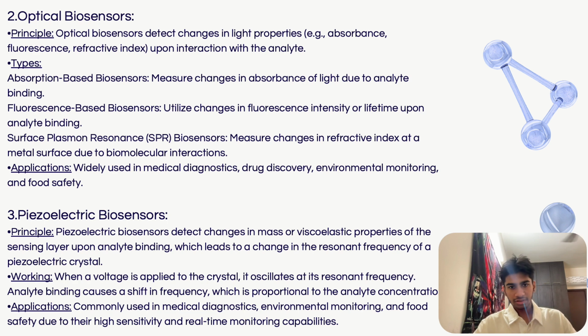Next, we have piezoelectric biosensors. The main working principle is that they detect the changes in mass or viscoelastic properties of the sensing layer upon analyte binding. This leads to a change in the resonant frequency of piezoelectric crystals. When a voltage is applied to the crystal, it oscillates at its resonant frequency. Now, analyte binding causes a shift in this resonant frequency, which is proportional to the analyte concentration. So the concentration can be measured based on this shift in frequency. They are commonly used in medical diagnostics, environmental monitoring, and food safety, due to their high sensitivity and real time monitoring capabilities.